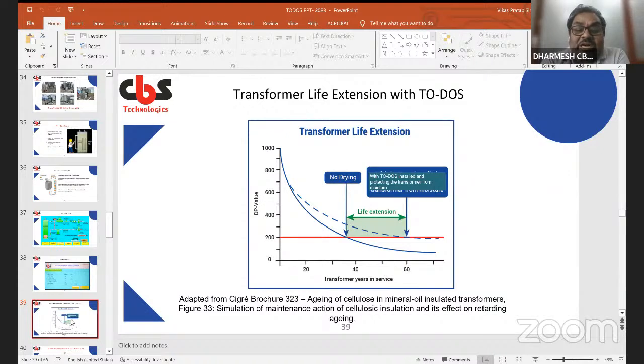This is adapted from the Cigre brochure 323, on aging of cellulose in mineral oil insulated transformers. This figure, Figure 33, is basically a simulation of maintenance of cellulosic insulation and its effect on retarding aging. This is taken from the Cigre brochure, which claims that transformer life can be increased up to 50 to 60 years.